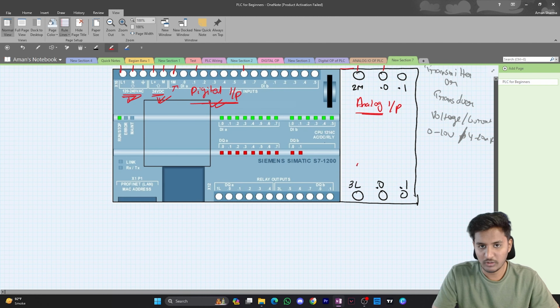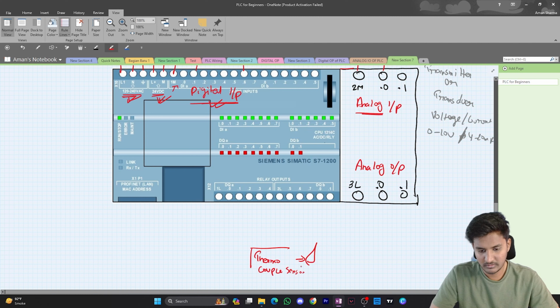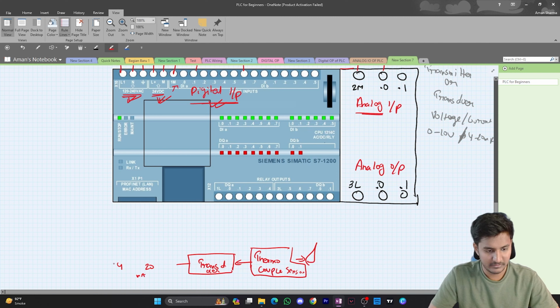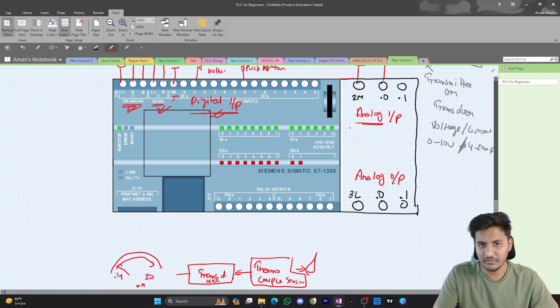So now let's move to the analog output. So assume we have a heat somewhere, okay, and the temperature is sensed by a thermocouple. This is a thermocouple sensor, which gives the output to our transmitter or transducer, which gives an output range from 4 to 20 milliampere. It will go like this. And assume this output is fetched here at the input of the PLC here.